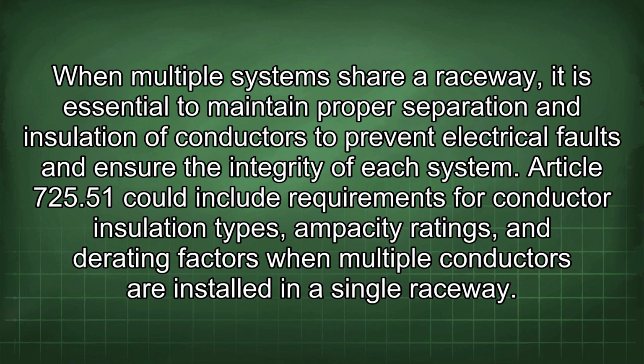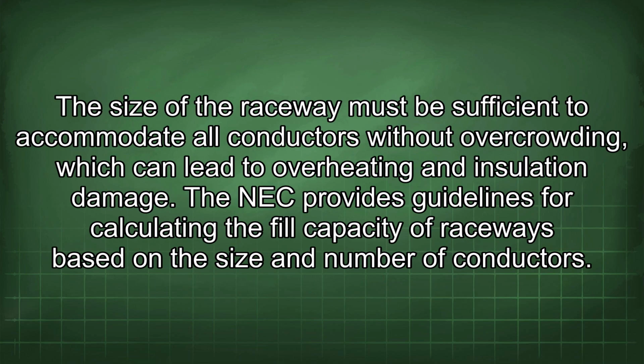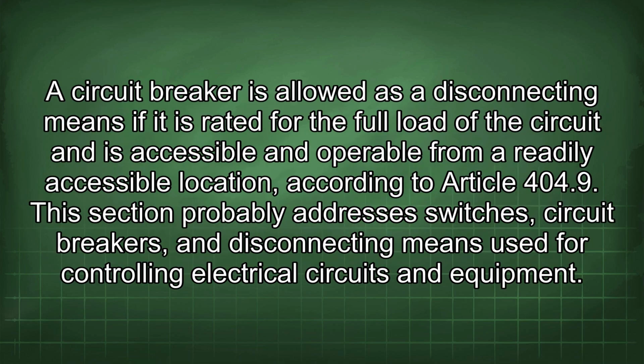Article 725.51 could include requirements for conductor insulation types, ampacity ratings, and derating factors when multiple conductors are installed in a single raceway. The size of the raceway must be sufficient to accommodate all conductors without overcrowding, which can lead to overheating and insulation damage. The NEC provides guidelines for calculating the fill capacity of raceways based on the size and number of conductors. A circuit breaker is allowed as a disconnecting means if it is rated for the full load of the circuit and is accessible and operable from a readily accessible location according to Article 404.9.